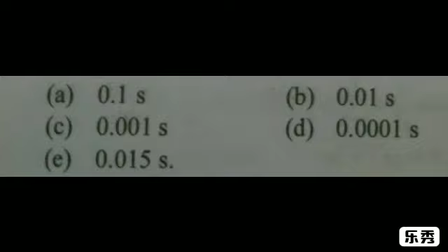0.0001 second. Now we have speed equal to distance divided by time, or time equal to distance divided by speed. So here the time is distance, that is 3 into 10 raised to minus 3 meter. It is given 3 millimeter. So 3 into 10 raised to minus 3 meter divided by speed 0.3 meter per second. And we need an accuracy of 1%. 1% means 1 by 100 of it. So the least count will be into 1 by 100. You can simplify this. 3 into 10 raised to minus 3 divided by 0.3 into 100. 3 and 3 can be cancelled. So it's equal to 10 raised to minus 4. This is the accuracy. This is the least count. Otherwise, 0.0001 second.